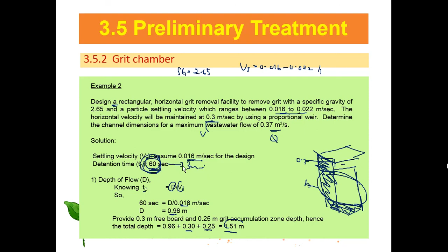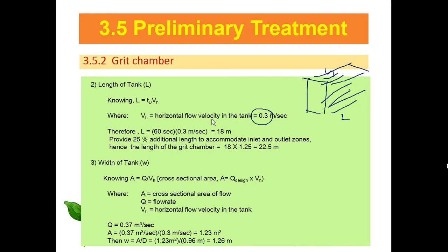Okay, so length here sama dengan TD darab dengan VH, flow nya sini, flow yang datang sini VH is 0.3, ataupun loading 0.3 meter per second. TD this one we assume tadi between 1 to 3 minutes lah. So multiply, so you get 18 meter. So 25% for the inlet and outlet zone. So you multiply dengan tambahan 25%, 1.25 je lah. Design dia 100%, so you tambah 25%, so you multiply dengan 1.25 lah. So the length ada 22.5 meter.